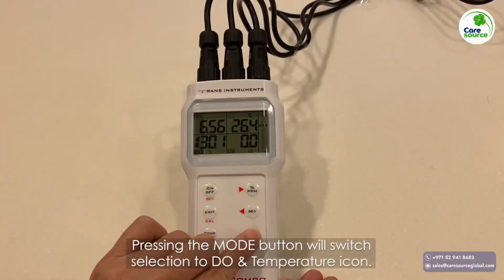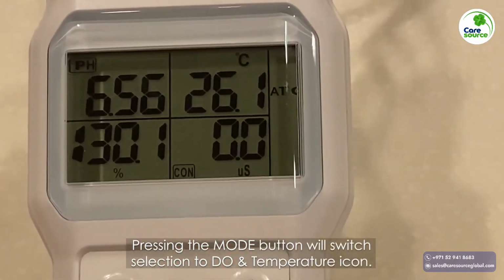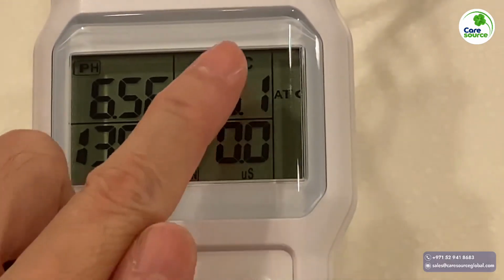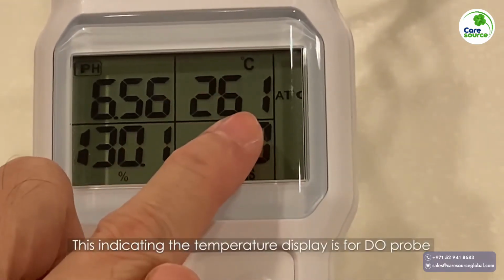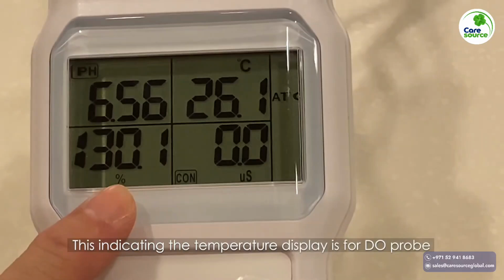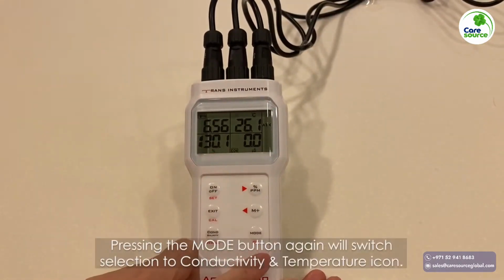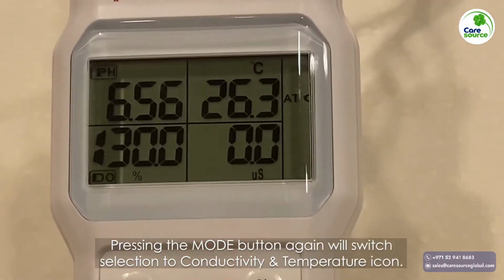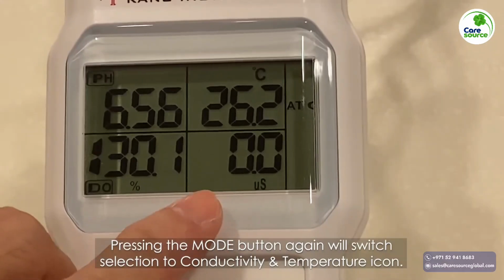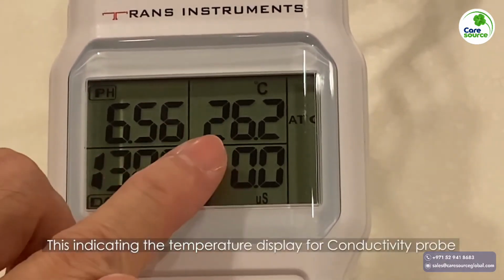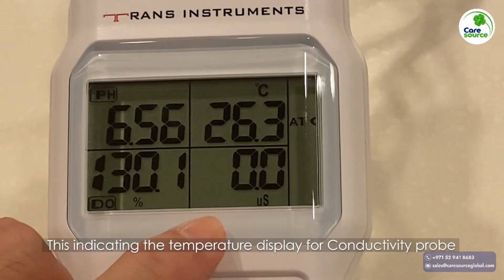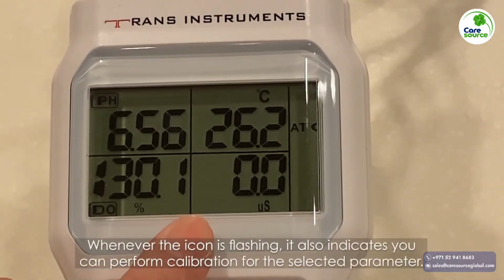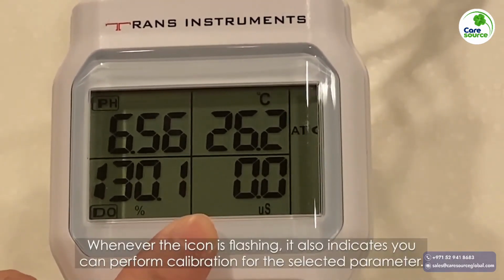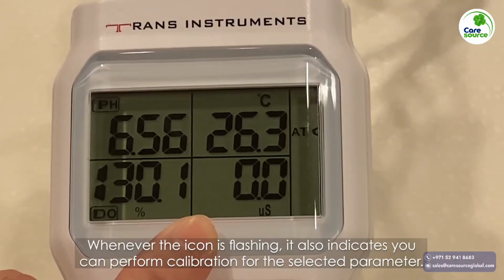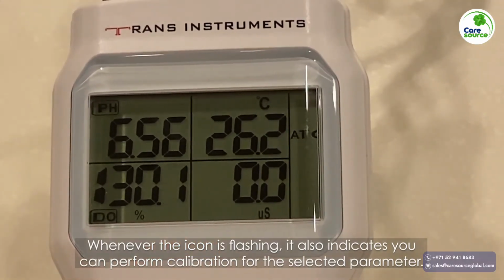Pressing the mode button will switch the selection to DO and temperature icon. This indicates the temperature display is for the DO probe. Pressing the mode button again will switch the selection to conductivity and temperature icon. This indicates the temperature display is for the conductivity probe. Whenever the icon is flashing, it also indicates you can perform calibration for the selected parameter.